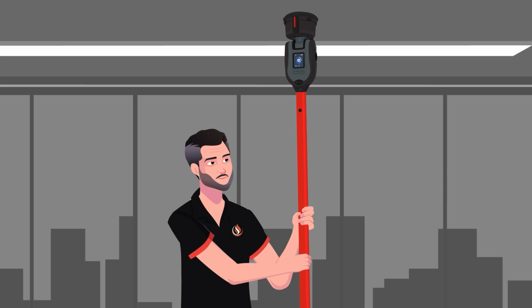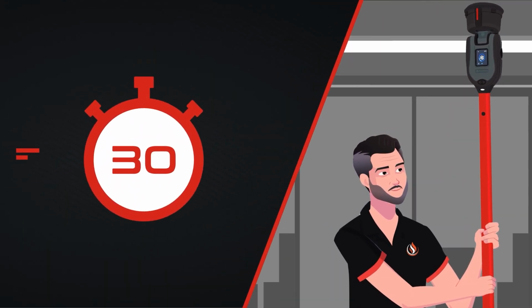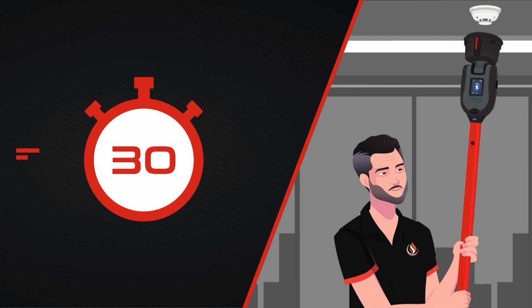After a smoke test, clearing automatically takes place, blowing air at the detector to remove any lingering smoke. The LEDs will flash white while clearing is taking place. Clearing will last for a maximum of 30 seconds, but can be stopped sooner by simply lowering the Testifire XTR2 away from the detector. Note, clearing is not enabled after a heat test.